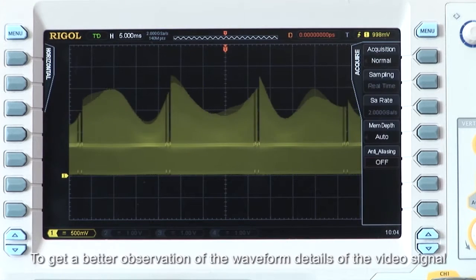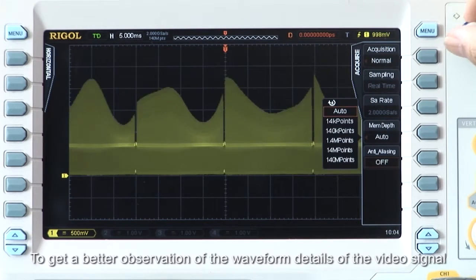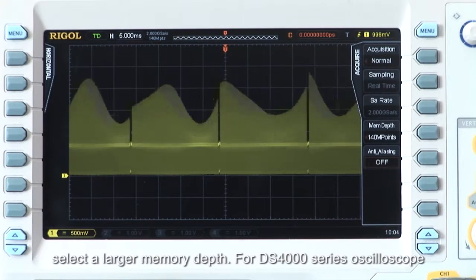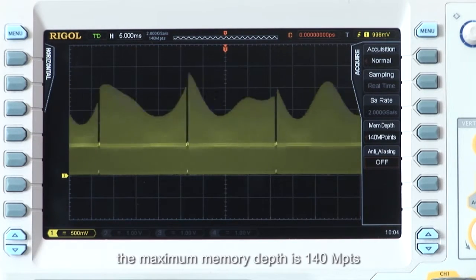To get a better observation of the waveform details of the video signal, select a larger memory depth. For the DS4000 series, the maximum memory depth is 140 mega points.